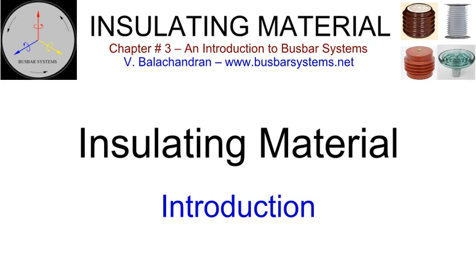Minnesota Mining and Manufacturing, 3M, US have developed green gas for grid, G3, which is not a greenhouse gas, and has been successfully used in gas-insulated bus in commercial operation. The minimum thermal class of insulation in busbar systems should be Class B, so that it meets the general requirements of international standards. A majority of all failures in a busbar system can be traced back to the failure of the insulator or the insulating medium. Insulator cost is a significant part of the overall cost of the busbar system.